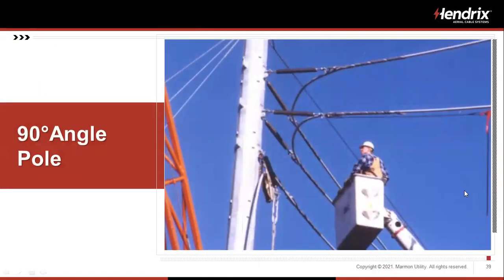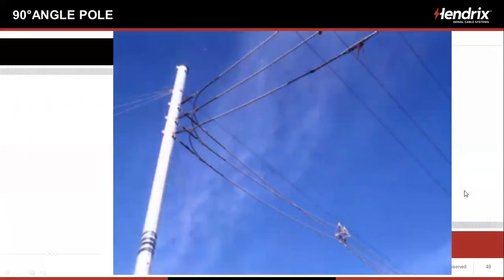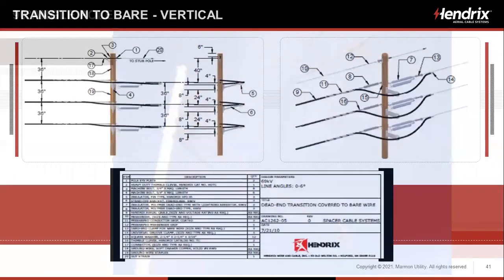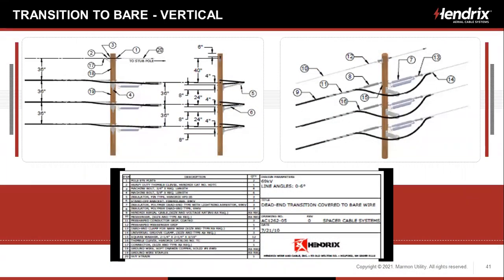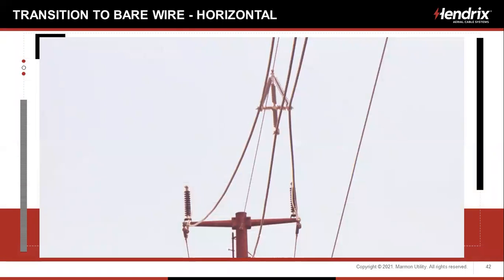Here's what it looks like during installation. And this is what it looks like after installation. So it's very clean. Here's a transition to bare wire. And again, this is a vertical transition. So we're coming through the preformed dead end grips, standing off that pole with a line post insulator, and just making a crimped transition on the other side to the bare wire. And you can see the lightning arrestor there that is necessary when we have a transition from bare wire to covered conductor, the same as you would use an arrestor on a riser pole. So that was a vertical transition.